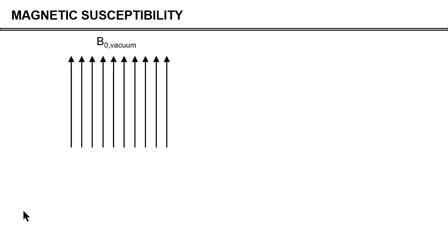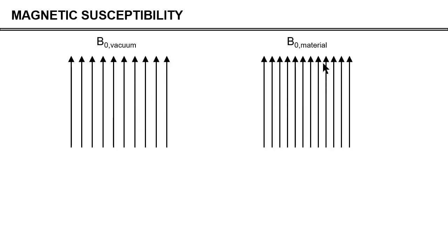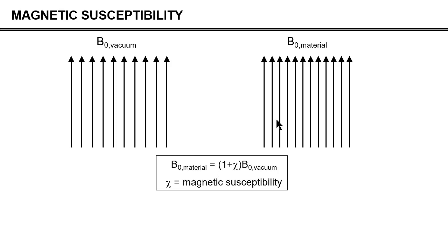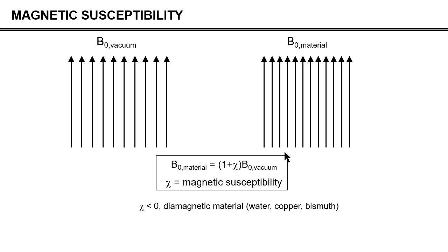Let's look in a little more detail at why we get inhomogeneity at a fundamental level. If we have a very homogeneous magnetic field in a vacuum — the field lines are perfectly equidistant, which implies homogeneous — and now we apply the same magnetic field into a material, you can see that the magnetic field is now slightly higher; the lines are a little bit denser. This is described by the equation that the magnetic field in a material is related to the magnetic field in a vacuum scaled by the magnetic susceptibility of the material. There are basically three types of materials. If the susceptibility is less than zero, it's called a diamagnetic material, and water is the best example.